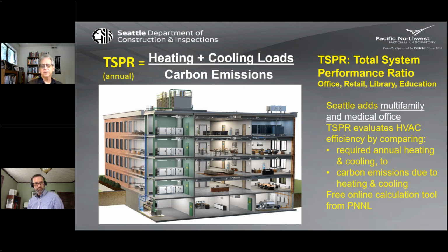Be aware that you have to meet efficiencies at certain temperatures—conventional heat pumps that just become a toaster oven below about 42 degrees are not allowed, and you have to account for the lousy insulation value of that through-the-wall unit. So we're moving people either to higher performing units if they're going to use a PTHP, or to find some better, more efficient, less wasteful system. They're kind of the very bottom of the barrel as far as quality of system goes, and it's hard to find a better efficiency—just putting that out there.